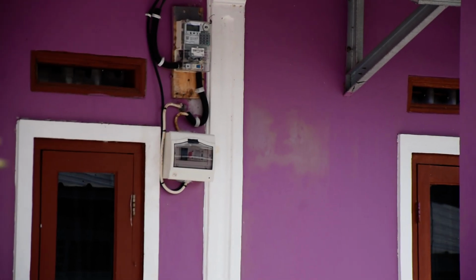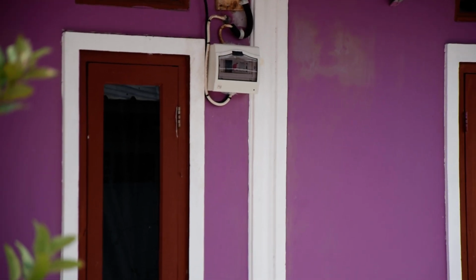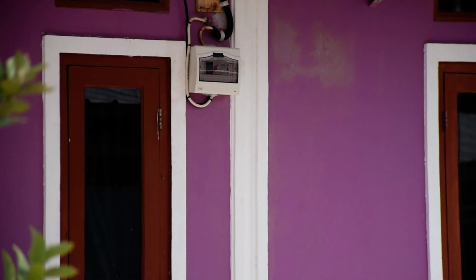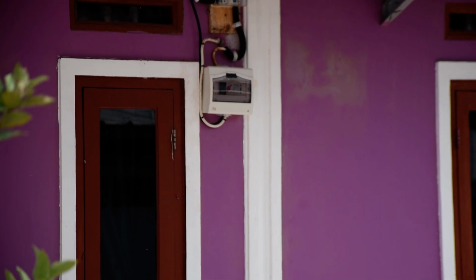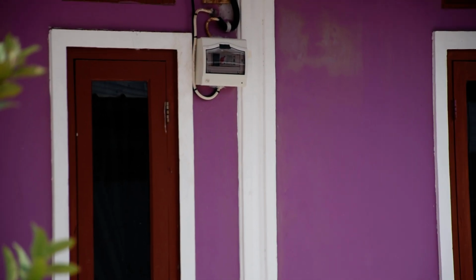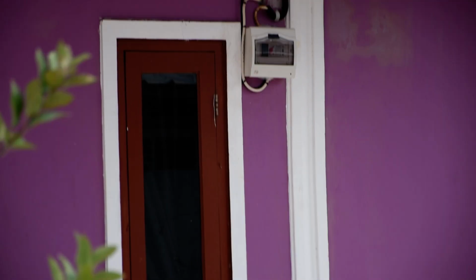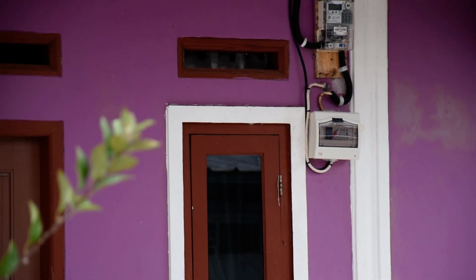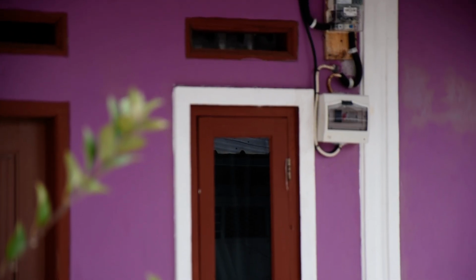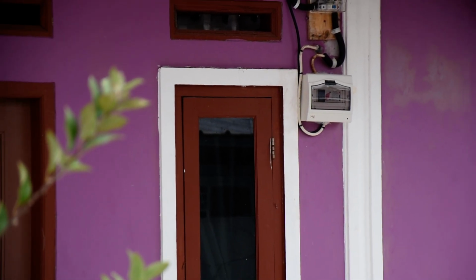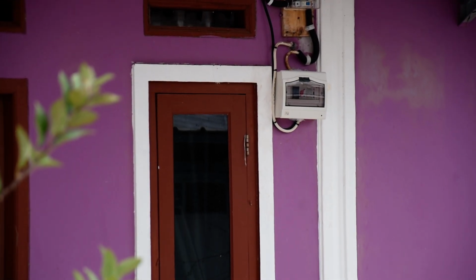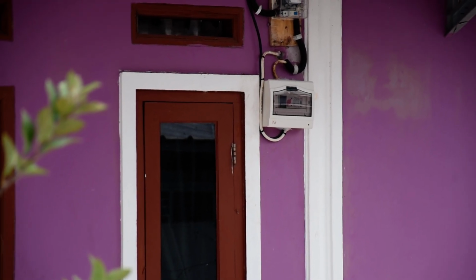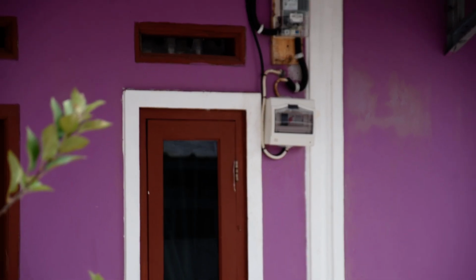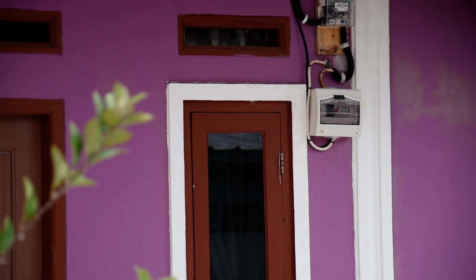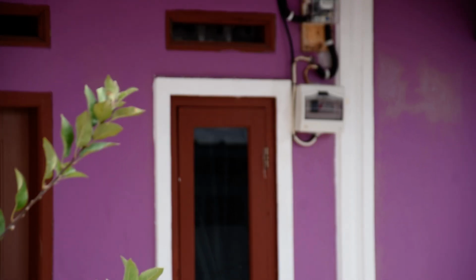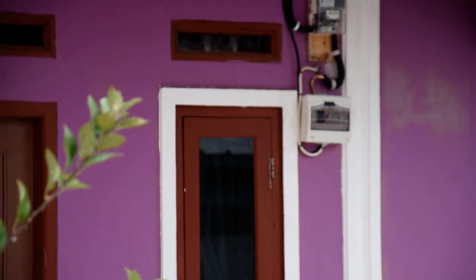That all got finished up and tested, and works exactly as it should. I also created a set of instructions for them on how to make sure the power is turned off to the inside of the house if they need to do some work inside. Because if they just turn off the breaker for the PLN, the wiring inside the house is still going to be live. So they can either switch off that line from the switchboard in my house, or switch the automatic transfer switch to manual mode before they turn off the PLN breaker, so it won't automatically switch across to off-grid backup. Hopefully they understood those instructions.